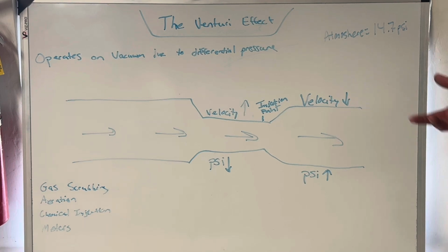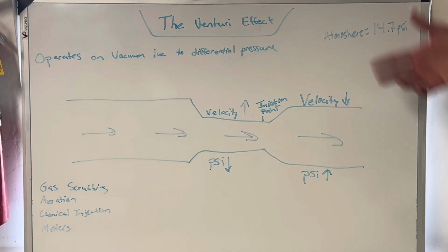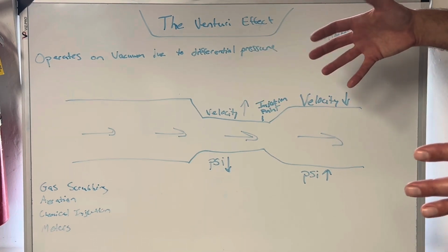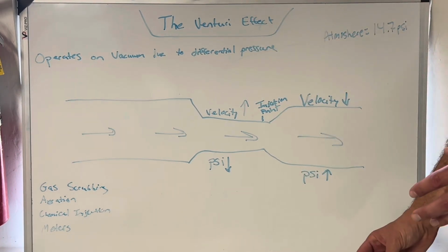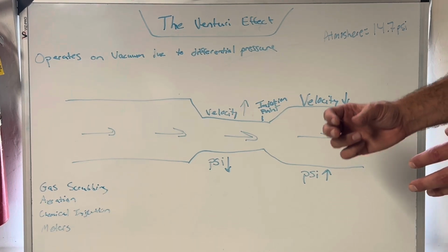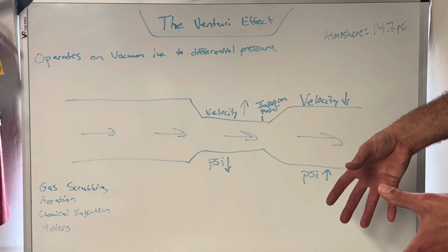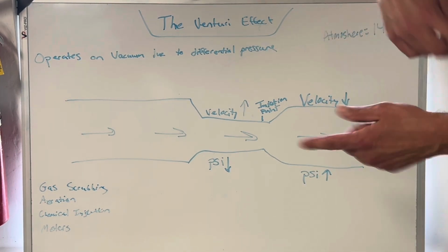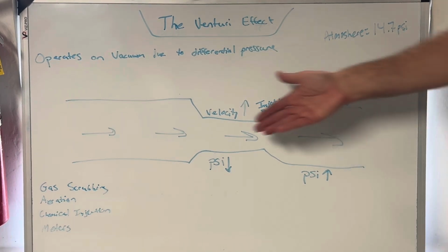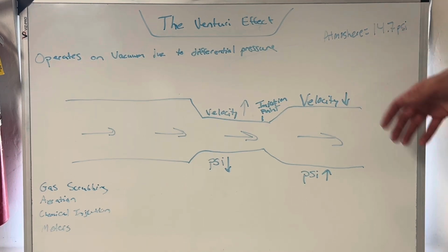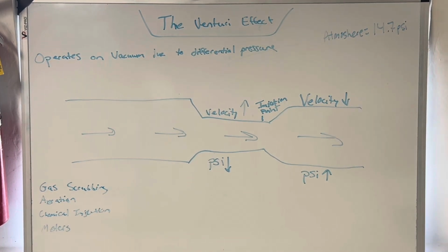Now, in my case, I don't do this. I'll give you just a quick sneak peek into our disinfection. What I do here is I have an open chamber. And what I mean by that is it's literally an open chamber of water that you could stick your hand in. And I have a chemical feed tube going into there, strapped to a chemical induction pump. Chemical is injected and introduced below the impellers of this pump, and it mixes it around. I don't have anything cool like this. I've got literally an open box of water and a pump in there stirring things up, and I inject right into that channel. That's how I do it.